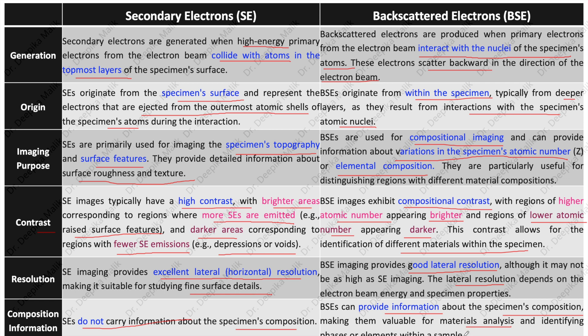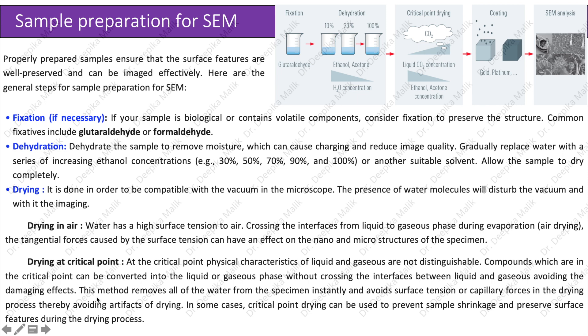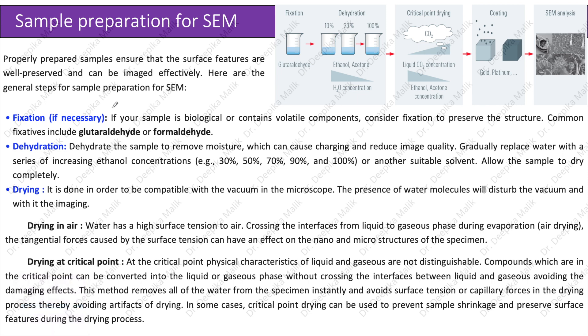Now let us discuss sample preparation for SEM. Properly prepared samples ensure that surface features are well preserved and can be imaged effectively. The first step is fixation, if necessary. If the sample is biological or contains volatile components, consider fixation to preserve the structure. Common fixatives include glutaraldehyde or formaldehyde.